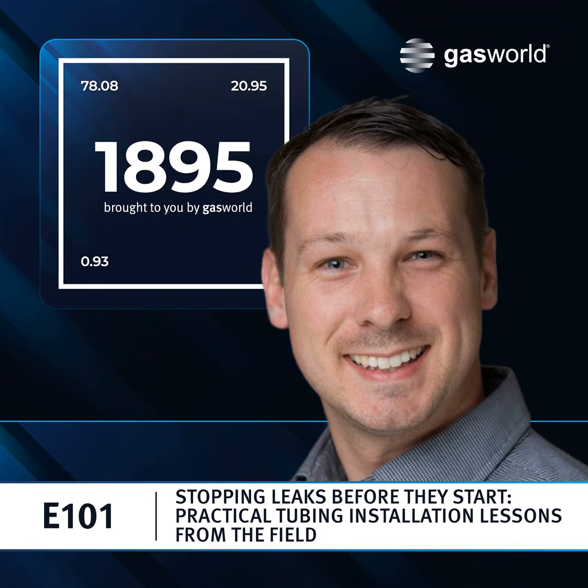Obviously, there's lots of manufacturers out there as well. So many times we'll see that there's intermix of different manufacturers' components. And not all of those components are engineered to work together. And so many times you'll have issues where you use different bits from different manufacturers that causes long-term issues and leaks. That can be missing components, inverted components, nuts and ferrules, things like that.